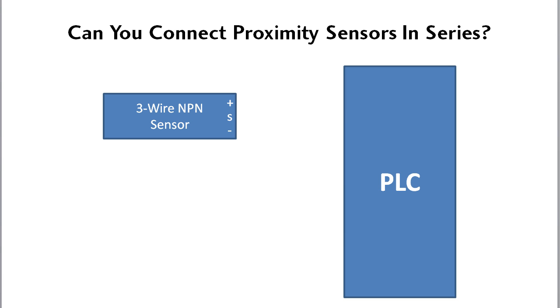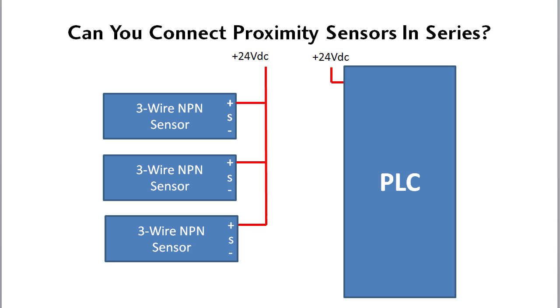If you have a three wire NPN sensor, then wire it like this. Connect the sensors and the PLC to 24 volts. Connect the first signal wire to the PLC and the negative terminal of that sensor to the signal wire of the next sensor. Do that again with the third sensor.